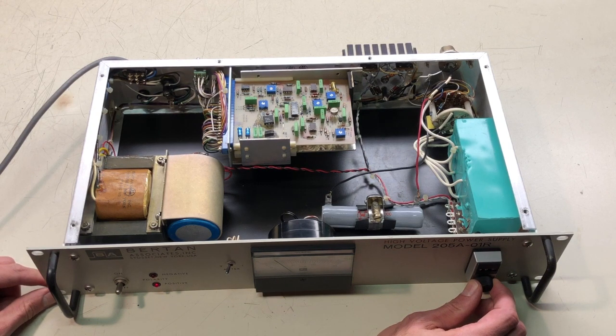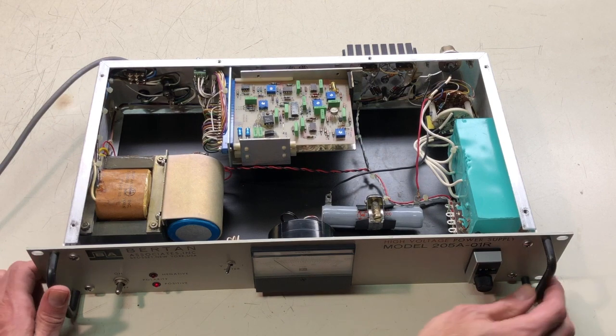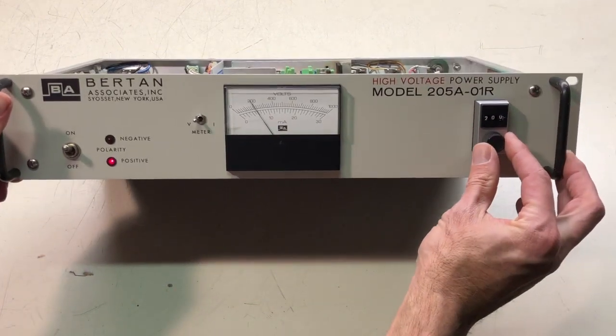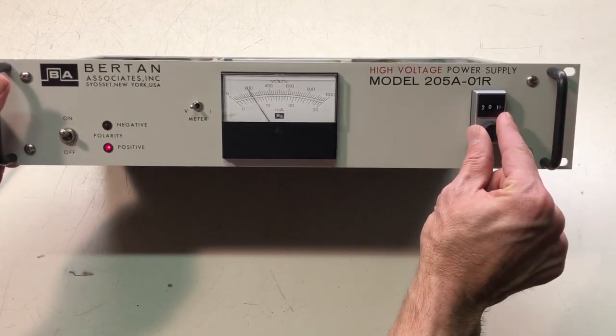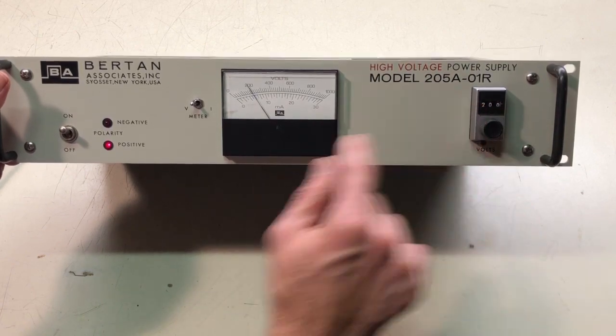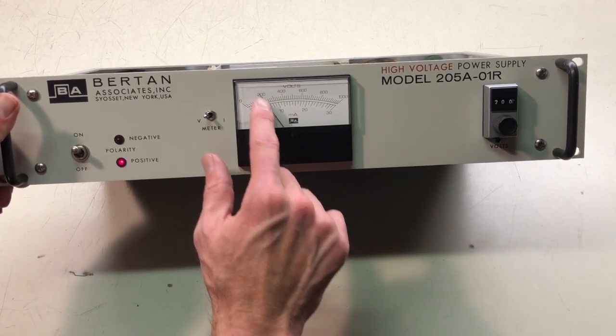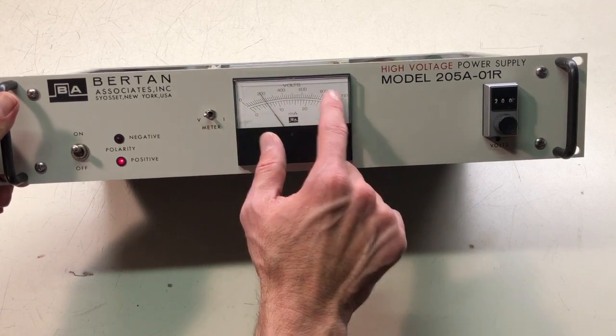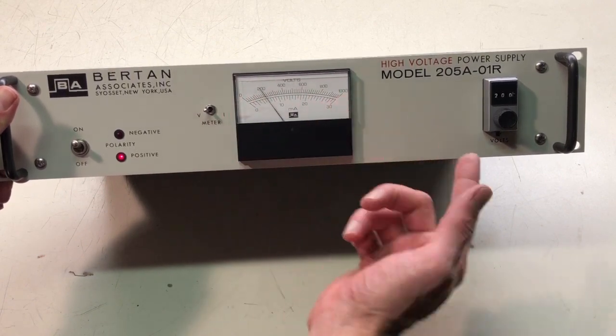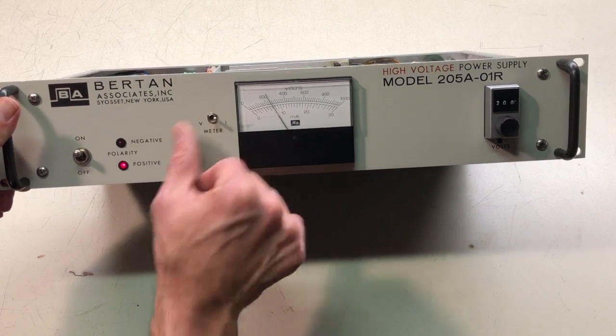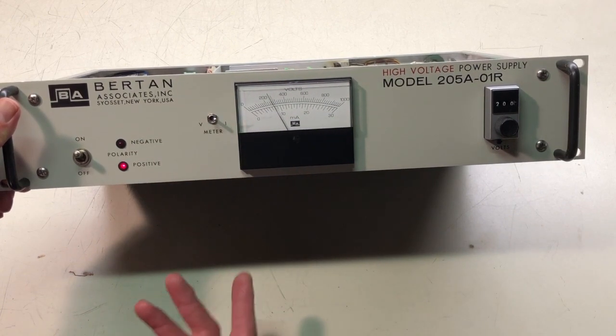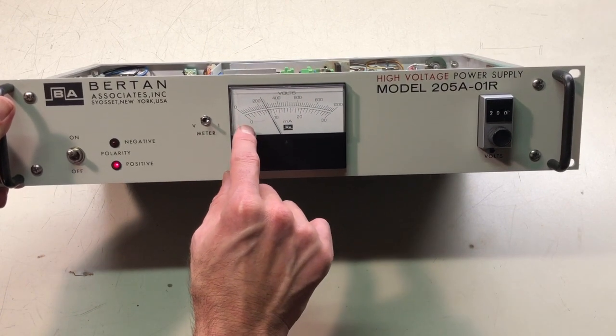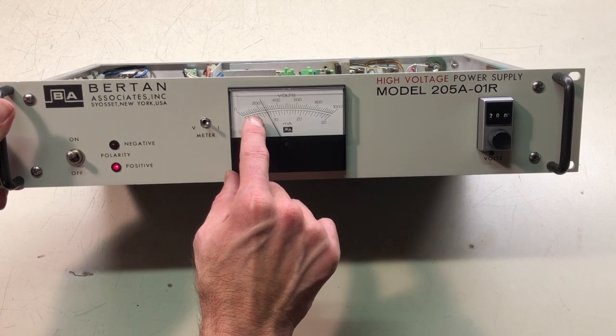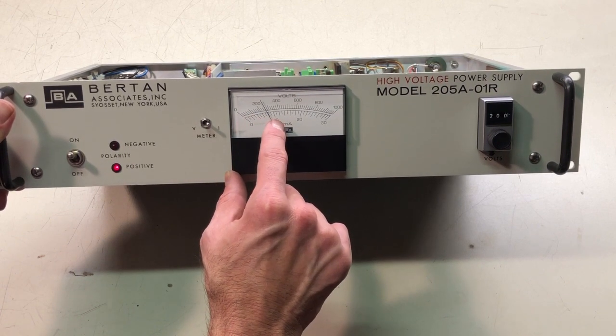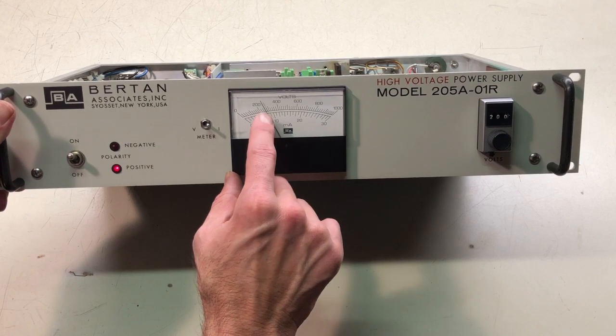That's pretty cool. It looks like the counter numbers match the voltage. Over here, these numbers look like 200, and we've got a 200 indication for voltage. Voltage is across the top scale, 0 to 1000. Flip it over to current. Spot on. Look at that: 2, 4, 6, 8, and then there would be 10. That looks really good.